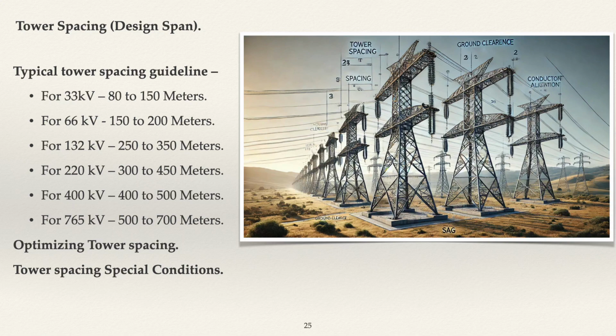Tower spacing, design span. Tower spacing refers to the distance between consecutive transmission line towers along the route. This distance is a critical design parameter as it affects the cost, structural requirements, and operational efficiency of the transmission line. The spacing is determined based on various technical, environmental, and economic factors. It depends on voltage, terrain condition, conductor type and sag tension, environmental condition, type of tower, regulatory and safety conditions, balancing cost and safety, and cross-section adjustments. Proper tower spacing is a key element in transmission line design, balancing safety, cost, and technical performance.